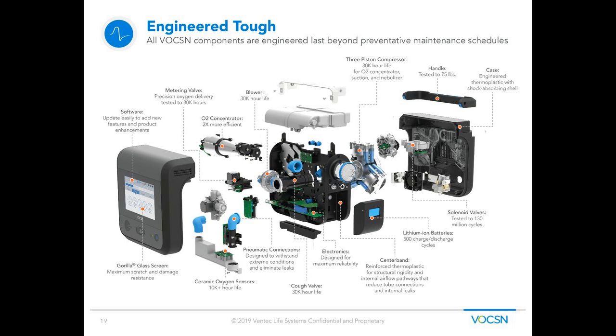VOCSN is serviced every 10,000 hours, or every 2 years, standard to your ventilator's preventative maintenance schedule today, but you're not only getting your ventilator checked, you're getting all five therapies looked at. It's really an apples to oranges comparison of traditional devices versus VOCSN's technology. Everything has been over-engineered to last well beyond the schedule you're used to, and ultimately everything in VOCSN is geared toward keeping the ventilation going.